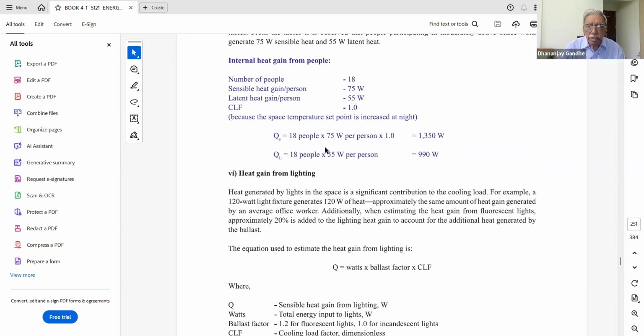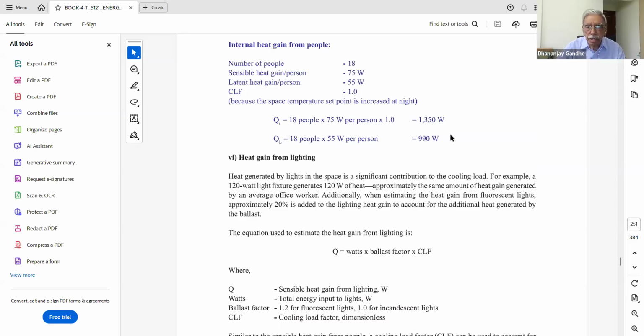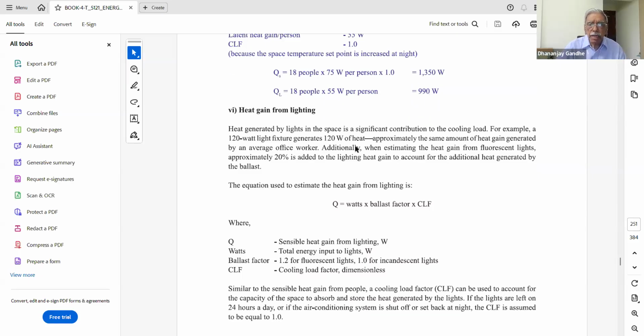So the total heat gain, latent plus sensible, is 1350 plus 990. So this is from the people. Similarly, if you have to calculate the heat gain from the lighting, obviously the heat that emanates from the lamps. So you have to know the wattage of the lamps, and you also know how much heat is developed by each lamp apart from the light. So that is the sensible heat.